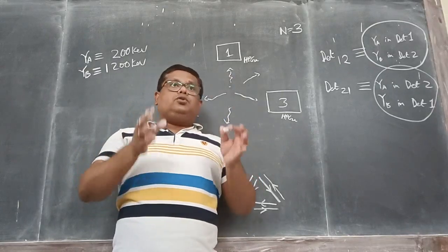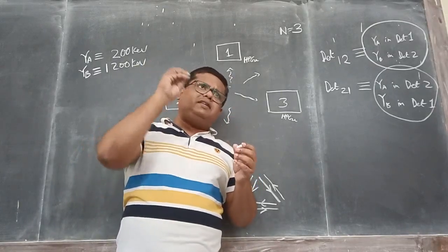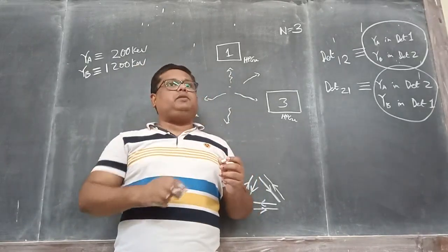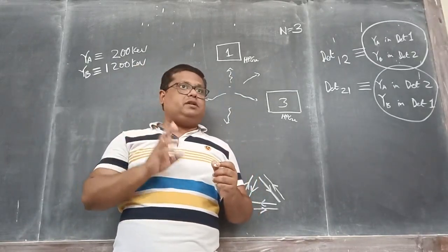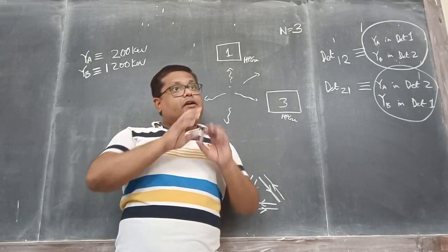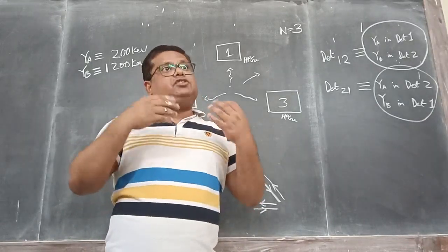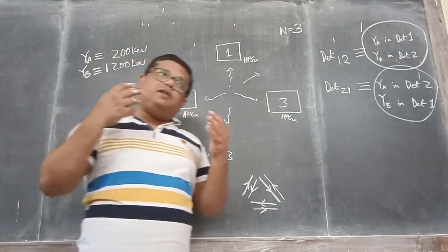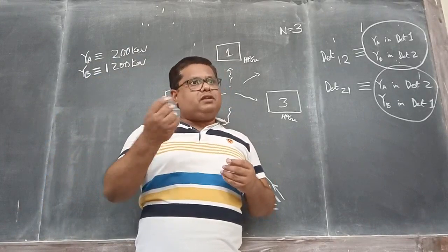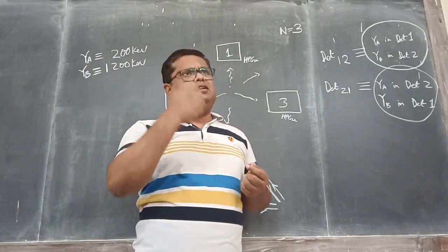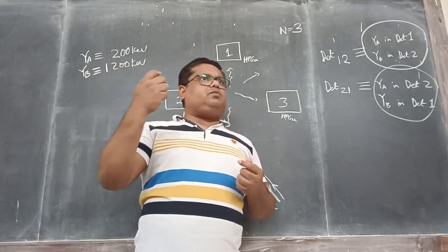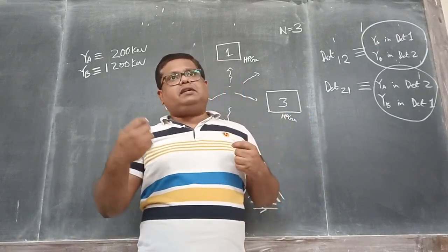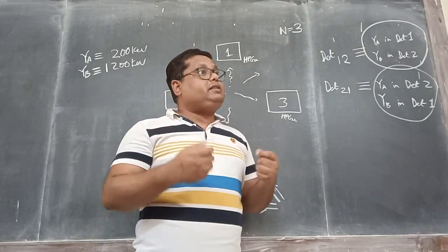Because of this, even though they are made by the same manufacturer, same time production, everything remains the same, their response will be different. This is very important, you must keep this in mind. So never assume that they will give identical response. And we have experimentally seen that. For example, the energy resolution will be slightly different. In one detector at 1 MeV, energy resolution will be 2.1 keV. In another detector, it can be 1.9 keV. They are different.